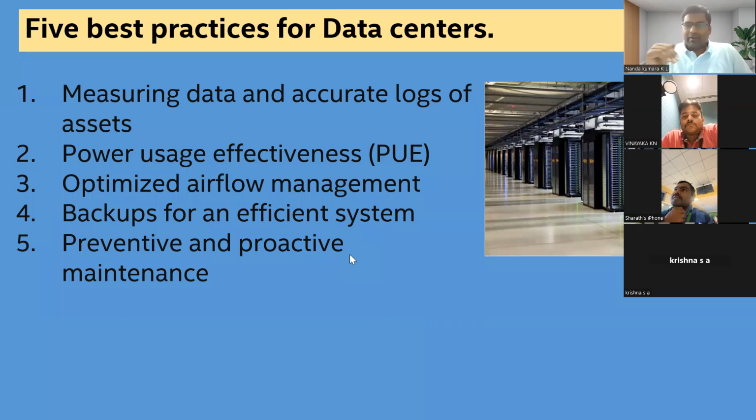See, nowadays people are talking about data center temperature. People used to talk 10 years back, 18 degrees. You should maintain 18 to 20 degrees. That concept is gone now. Now, ASHRAE, the American heating and ventilation standard system, recommends that a data center should be about 25, 26, 27. You can go up to your desired limit, as long as it does not impact the servers' operation. Anything above that, that is the ASHRAE standard now, so that we are not overcooling the data center. The equipment is running up to the optimization level. So airflow optimization is also one of the important points.